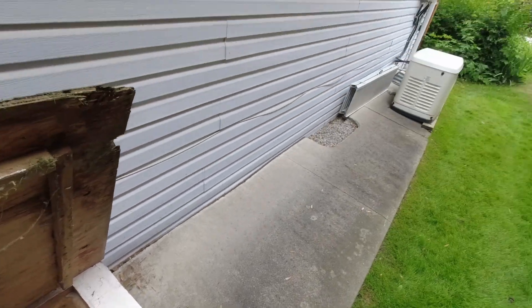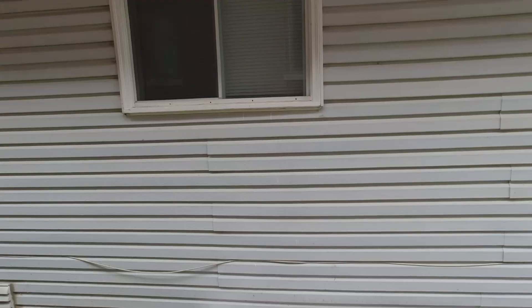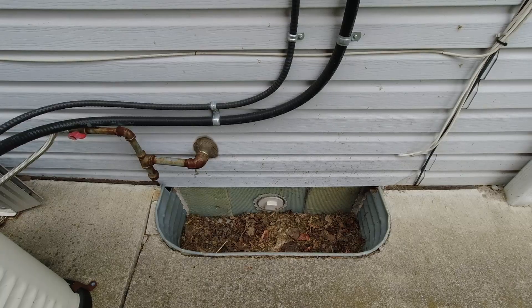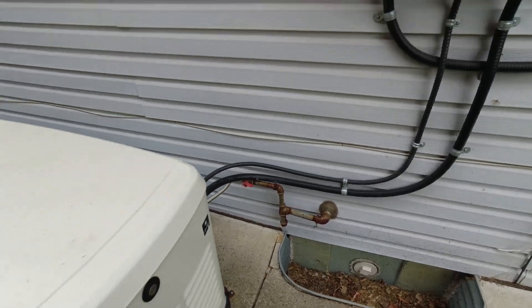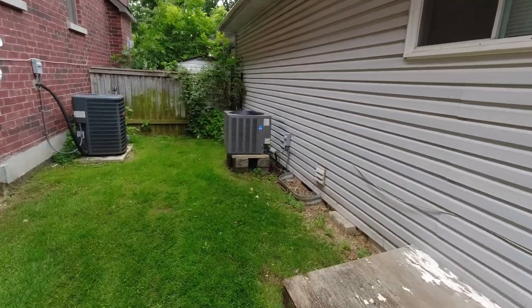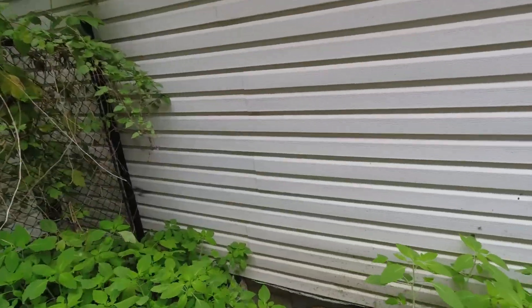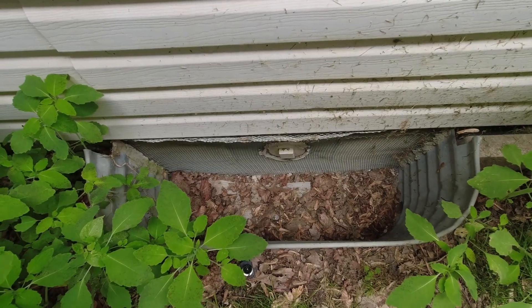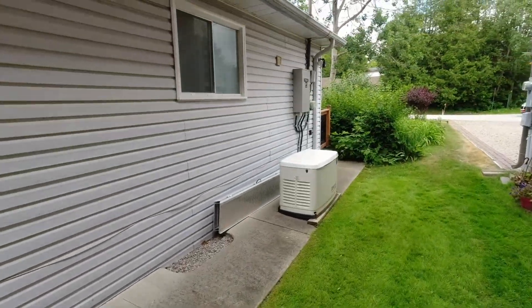So the CO either came through that vent over there, or it came through here. He says these windows — I'll show you in a second. This vent for the crawlspace — he never opens those because inside the crawlspace was encapsulated with spray foam years ago, so those caps are on there permanently. Basically, when I say encapsulate, all the walls are spray-foamed inside, so even though it's a crawlspace, it's a conditioned area. So that door has to be fixed and closed, that cap has to be replaced, and the generator has to be relocated.